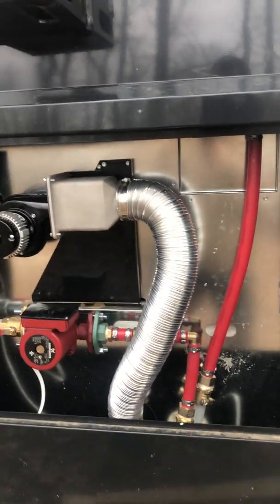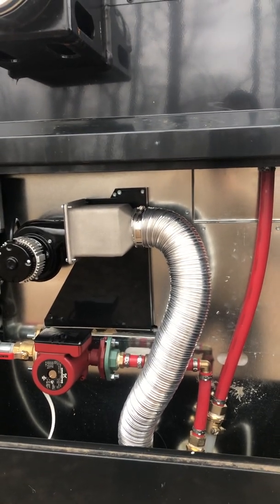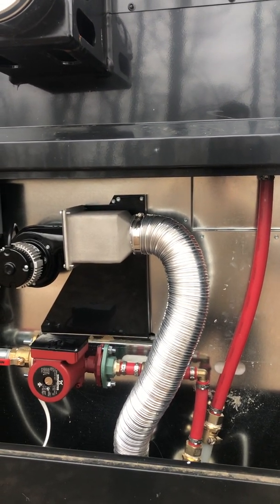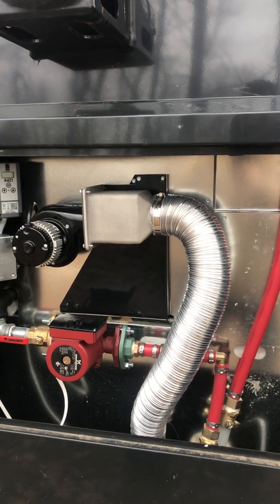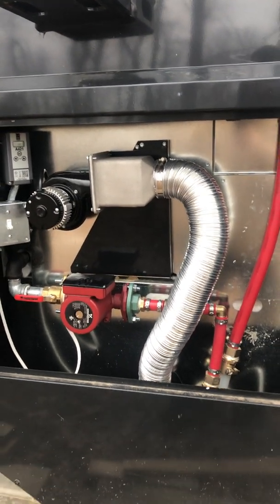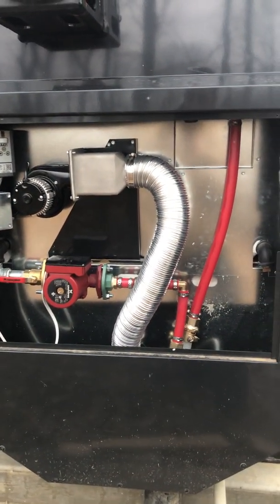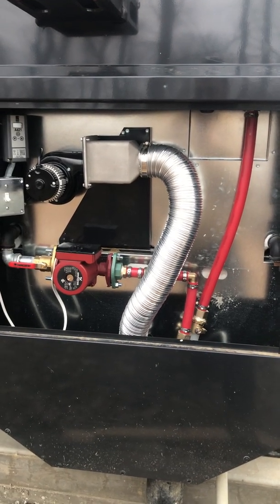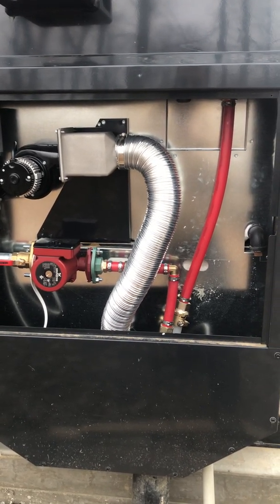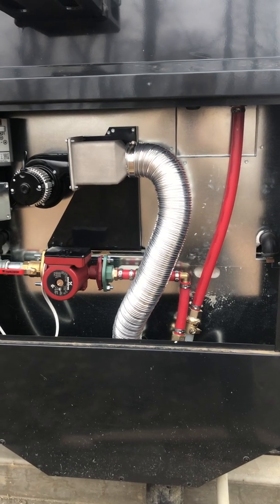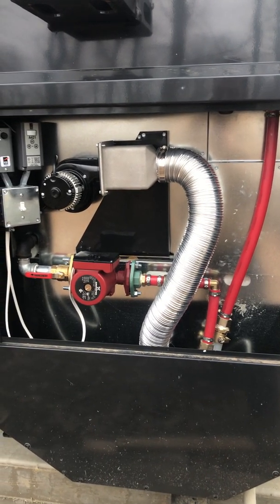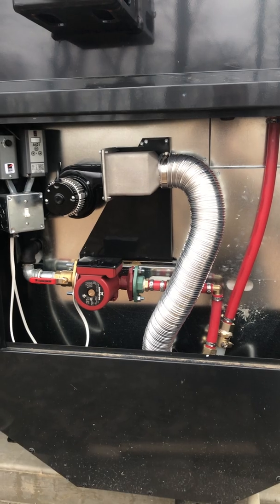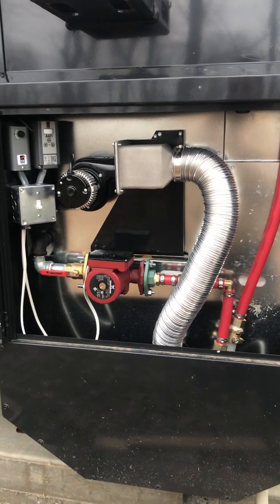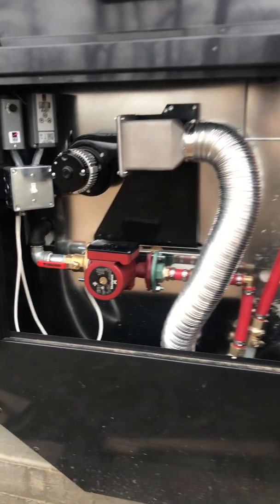Now, I will say, when I originally thought about this, I thought the hottest water inside the water jacket will be at the top, so the supply needs to be the top and the return needs to be the bottom. But to get everything mixed properly, I've been talking to some guys that had set it up this way - they're pulling water from the bottom, and then the supply water goes in the top, and it mixes it better. So I'm going to give this a shot and see how it goes, but this is how I'm setting it up originally.